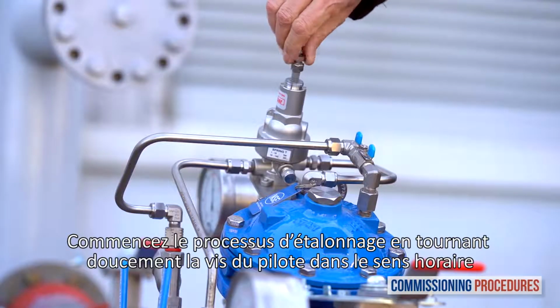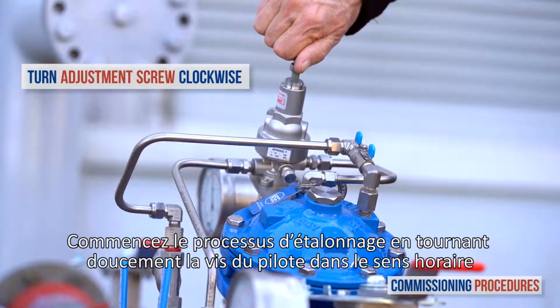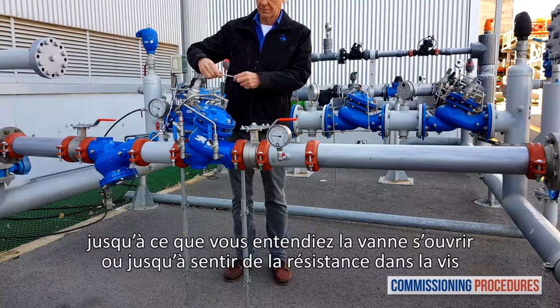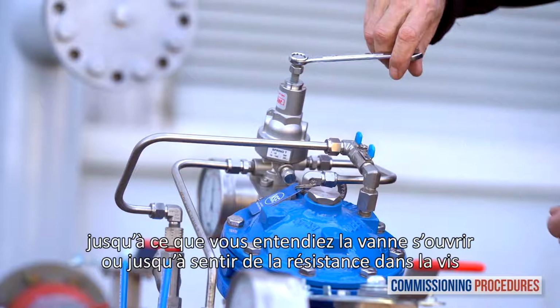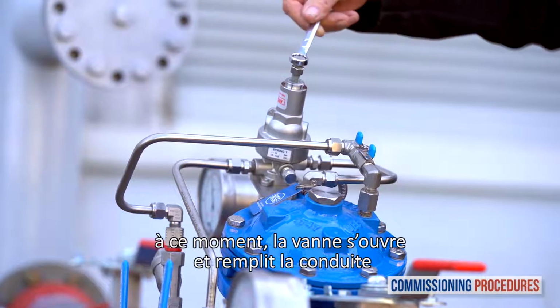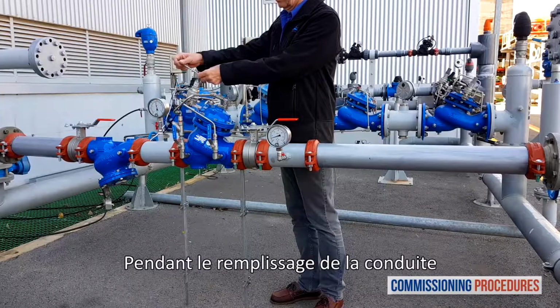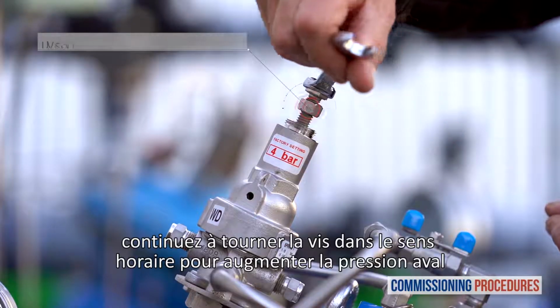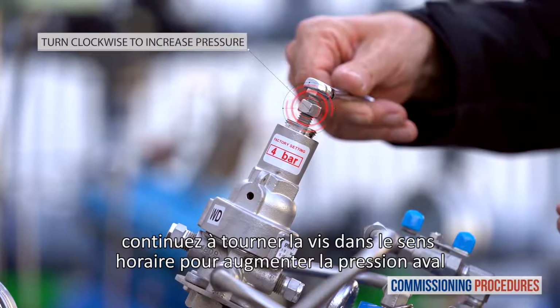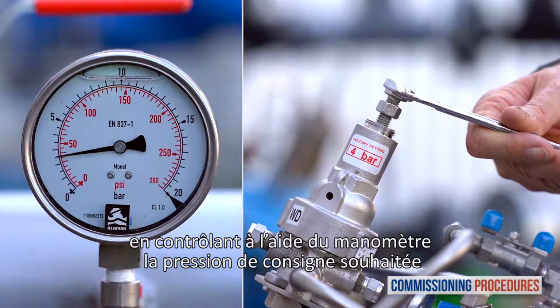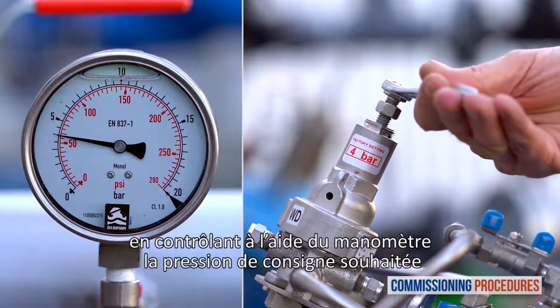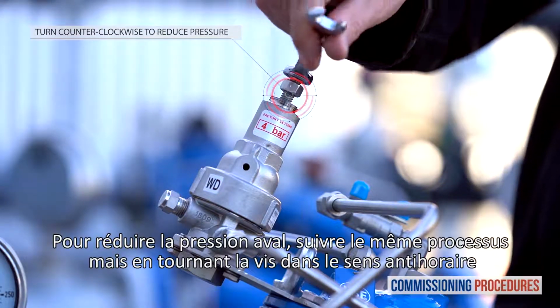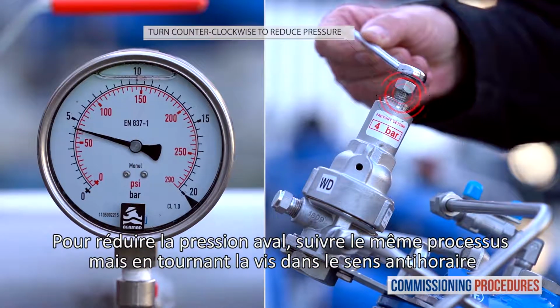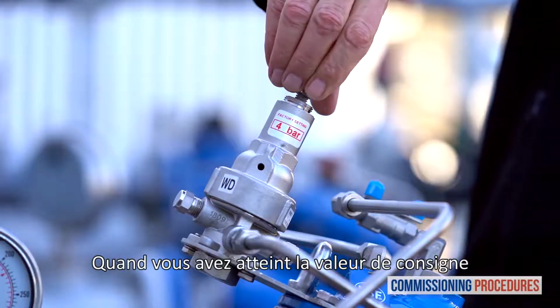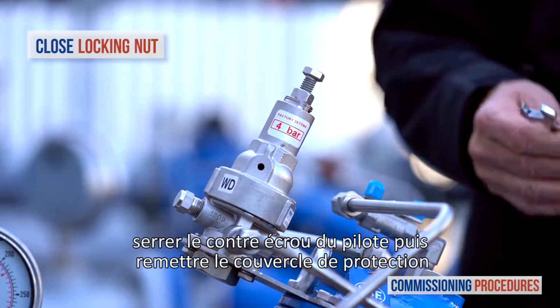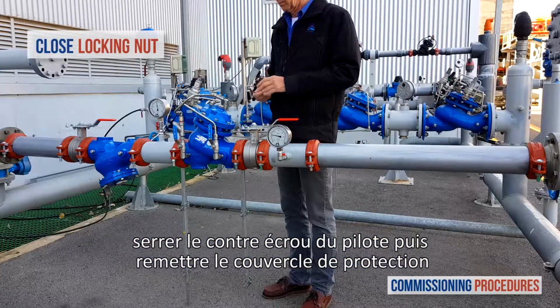Begin the pressure calibration process by slowly turning the pilot adjustment screw clockwise until you hear the valve opening or feel a resistance at the pilot's adjustment screw. At this point, the downstream consumer's pipeline will start to fill. When the consumer's pipeline is full, slowly turn the adjustment screw clockwise to increase the downstream pressure. Do this while monitoring the downstream pressure gauge until you reach the required pressure. To reduce downstream pressure, follow the same process, but in this case, turn the adjustment screw counterclockwise. Once you have reached the desired downstream pressure, close the pilot adjustment screw locking nut and replace the protective cover.